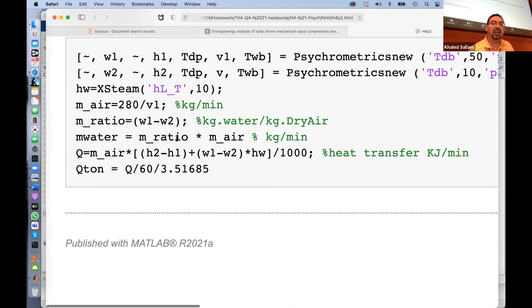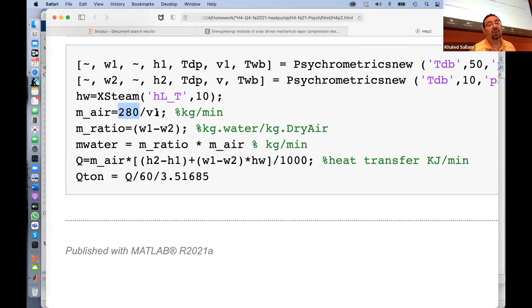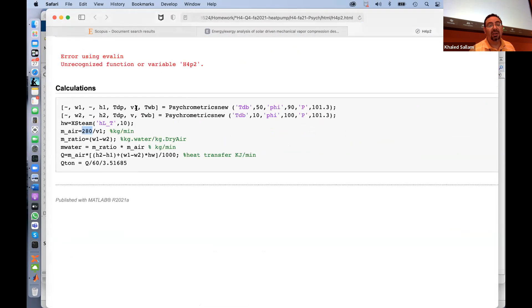And to get m air, remember this was in cubic meters per minute. What we needed is kilogram per minute, so I need to divide over the specific volume. I get the specific volume from the psychrometric chart, just like I got my W1, I can also get my V1, specific volume. So this line will give you M air, and you just have to add this line - it's M ratio times M air, and that will be kilogram per minute.